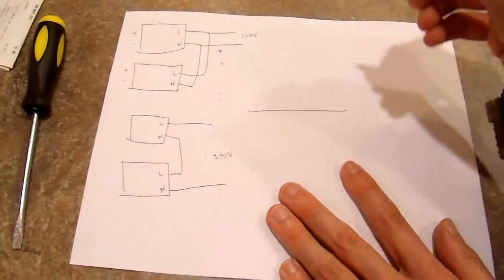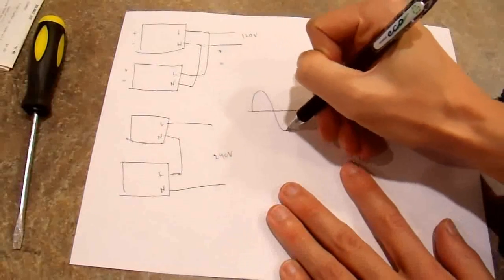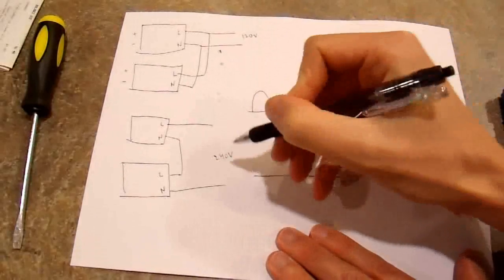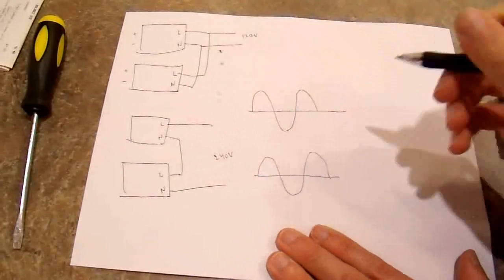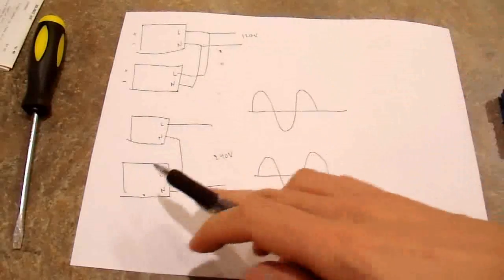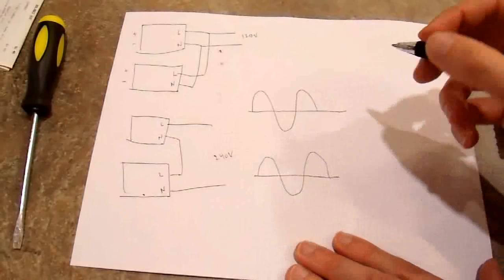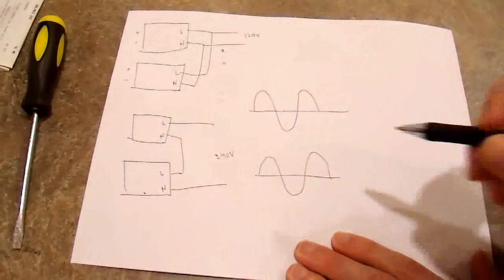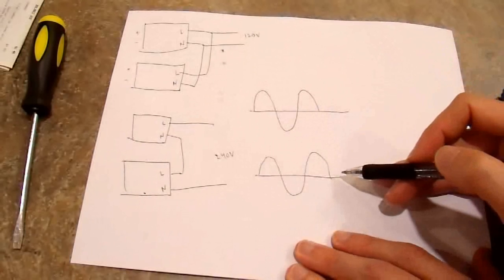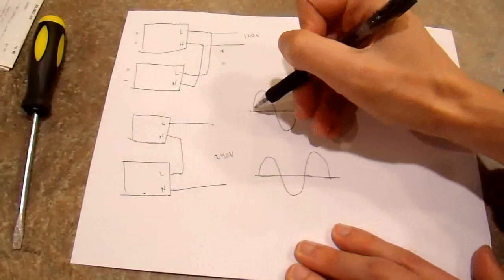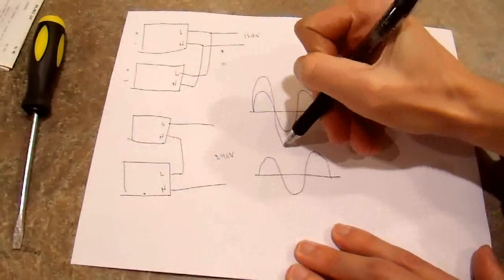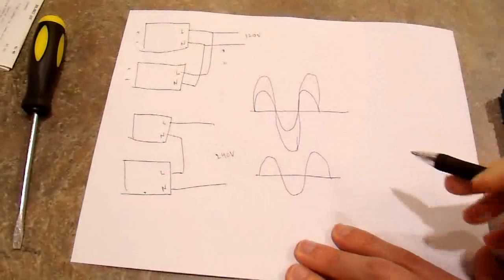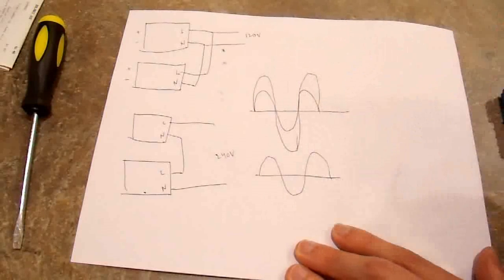A little drawing here of what I mean. If you have the output of this inverter up here, the output of this inverter down here, they're both sine waves, they're both 120 volts, peaking at about 170 volts. If they're perfectly in phase, like we'll imagine these two are perfectly in phase, then this one, once it's superimposed on top of this one, will end up doubling the voltage in every case. And you'll end up with twice the voltage, 240 volts AC.